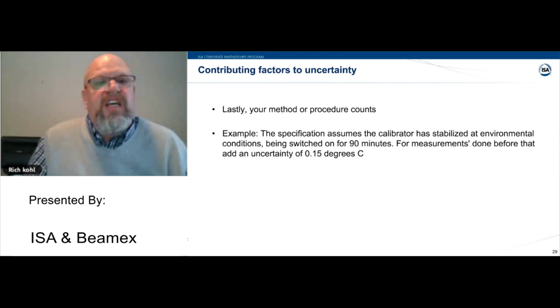So, lastly, I want to talk about the procedure you're using. These are your methods. It has a lot to do with how your people have been trained to do the particular calibration, and just knowing what they're doing, knowing their test equipment. So an example of this would be a specification that assumes the calibrator has been stabilized at environmental conditions by being switched on for 90 minutes. That's a long time, but for the purpose of discussion, 90 minutes. For measurements done before that thermal equilibrium has been reached, you have an uncertainty adder of 0.15 degrees C.